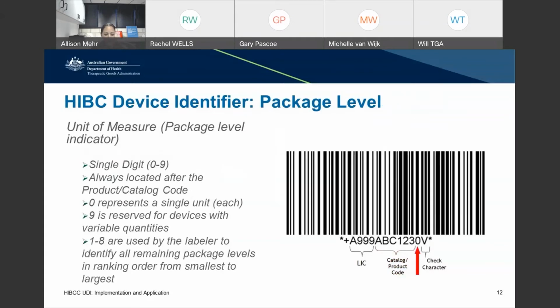And the last field of the HIBC DI is the unit of measure or package level indicator. This is a single digit from 0 to 9, where 0 will always represent a single unit and 9 is reserved for devices with variable quantities. The remaining numbers can be used to identify all of the remaining package levels of a specific device in ranking order. And again, this is something that's assigned by the labeler. HIBC does have guidelines for how this is used, though.